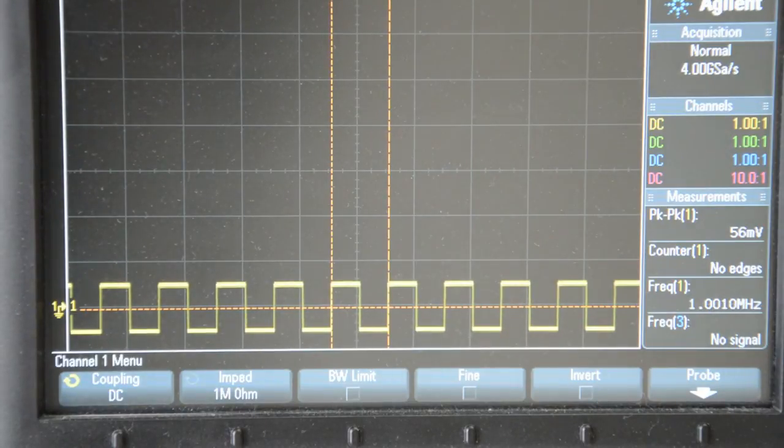So, again, this is exactly doing what it should, the 50mV peak-to-peak checks out, so I don't have any doubts that there is anything wrong with the log detector board.